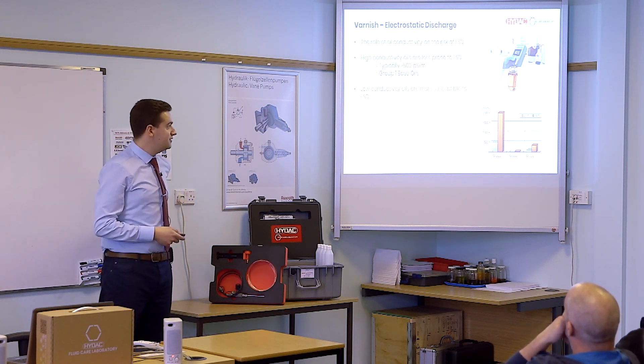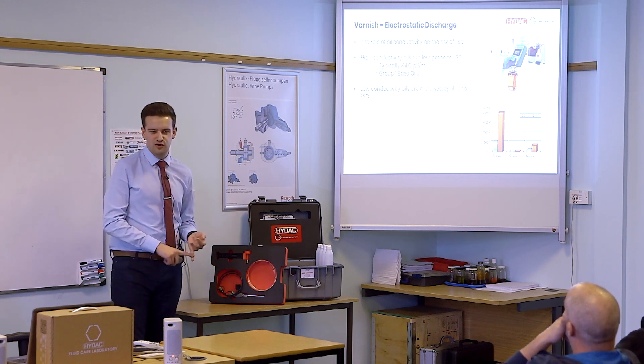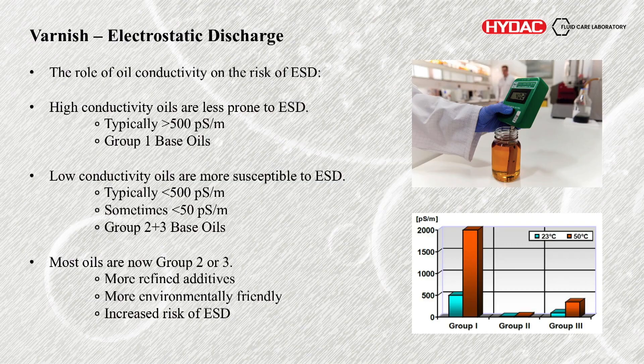As we've refined the fluids and made them better for industry — more capable at lubricating — and as we've tailored the additive packages, conductivity as a side effect has lowered. Now we might see typically less than 500 picosiemens per metre, sometimes as low as three or four pS, which is almost guaranteed a risk of discharging. That's the Group 2 and 3 base oils we're seeing now, and most oils you're going to get now are going to be Group 2 and 3.